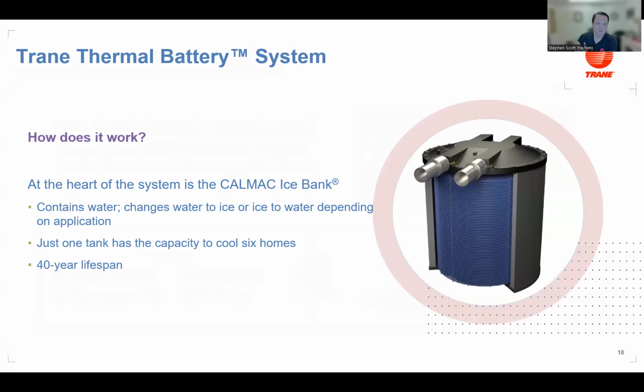For thermal batteries, we purchased Calmac about seven years ago. I've been in this business for over 40 years. It's a tank of water filled with about 5 kilometers of plastic tubing, with glycol inside the tubing. You freeze ice when rates make sense, and melt ice when rates make sense. One tank has enough capacity to cool approximately six homes, depending on the temperature.